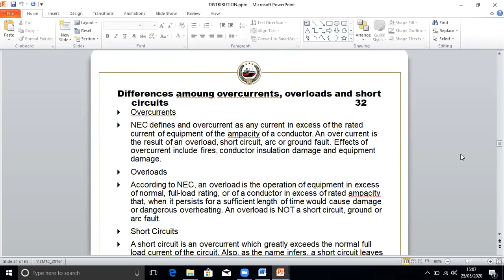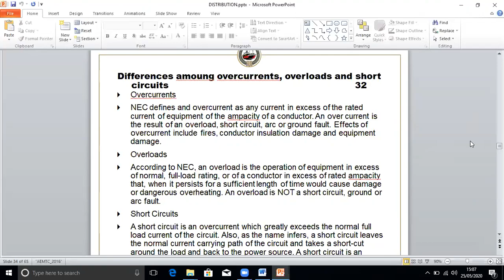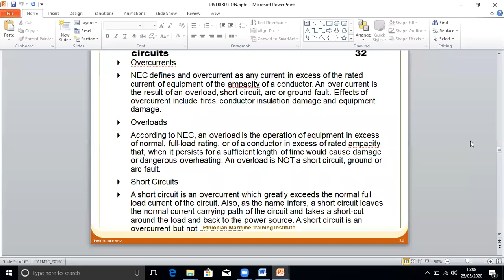Overload means operation of equipment in excess of the normal or full load rating, or a conductor in excess of the rated capacity, that, when it persists for a sufficient length of time, would cause damage or dangerous overheating. Overload is not a short circuit or a ground or arc fault. Short circuit is an overcurrent which greatly exceeds the normal full load current of the circuit. As the name infers, the short circuit leaves the normal current carrying path of a circuit and takes a shortcut around the load and back to the power source. So that is why it is called short circuit. It takes a short path to the power source.